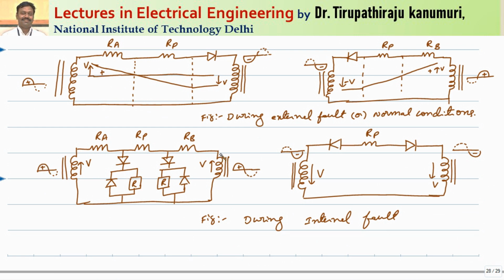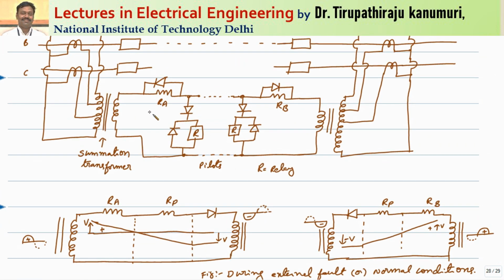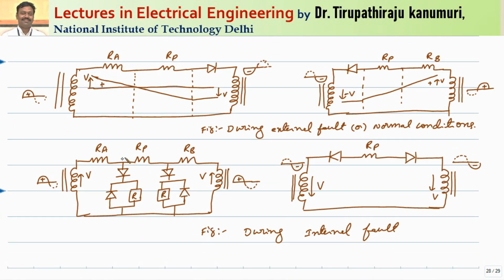So at both sides the voltage is positive, because the fault is fed from both the sides for internal faults. When the fault is fed from both sides, both sides the voltage is positive, this diode is reverse biased and this diode is also reverse biased. So automatically the current will pass through this RB and through RA, and in between the pilot resistance will be there. You can see here RA is there, RP is there and the pilot resistance is there. As the voltage is positive on both sides, there will be some voltage drop across this RB also. So we can tell this point as well as this point will be positive voltage when compared to the second side, agree with me?